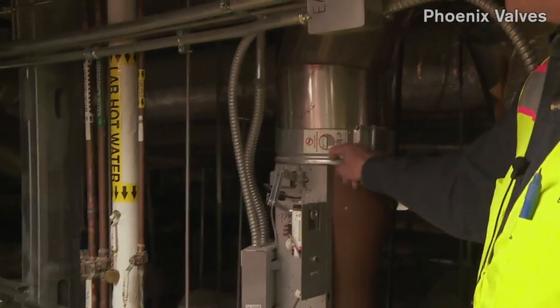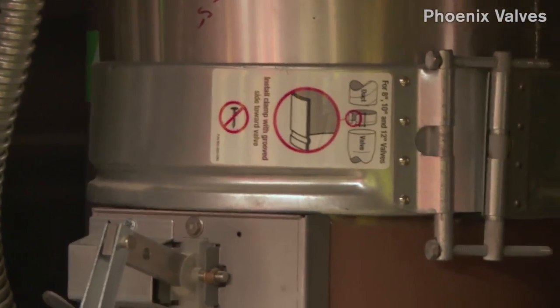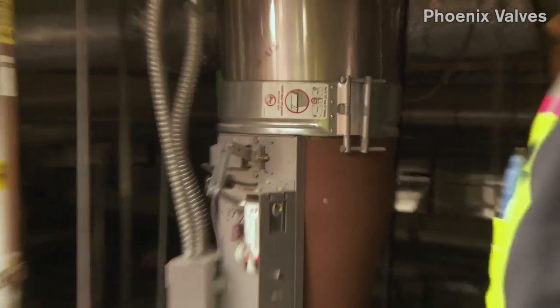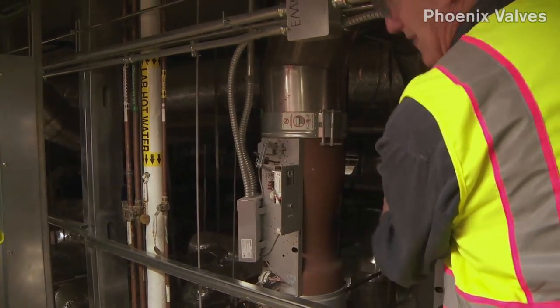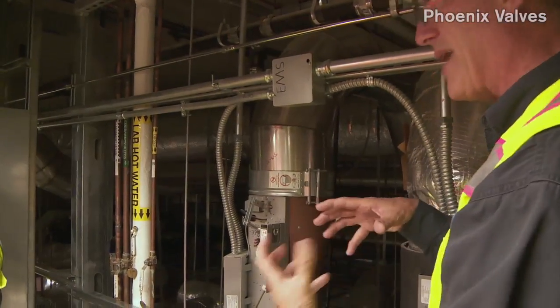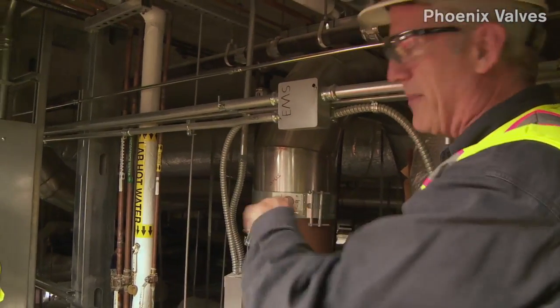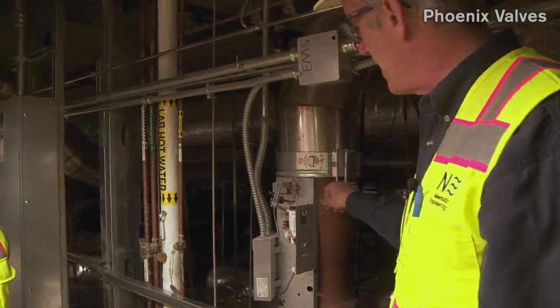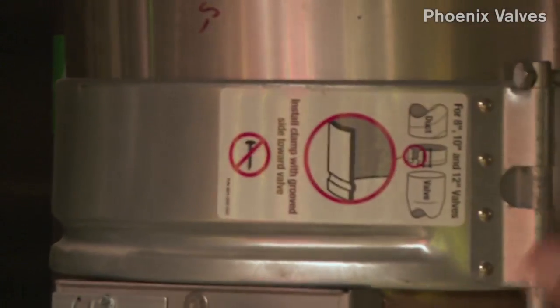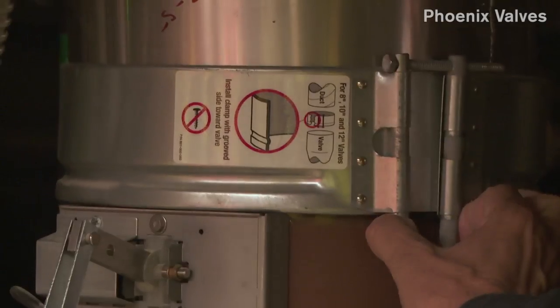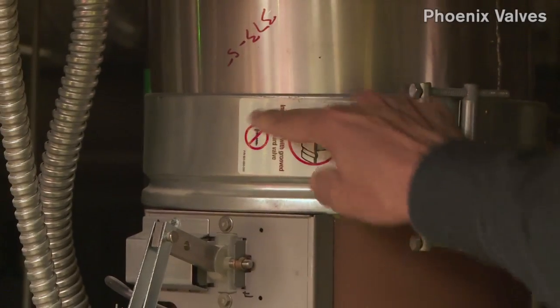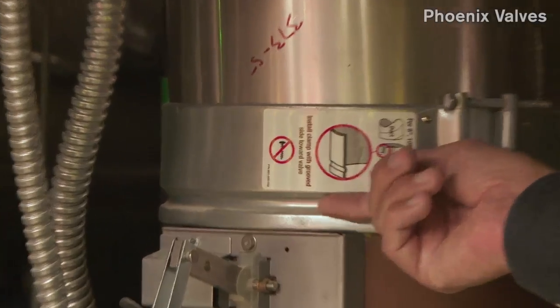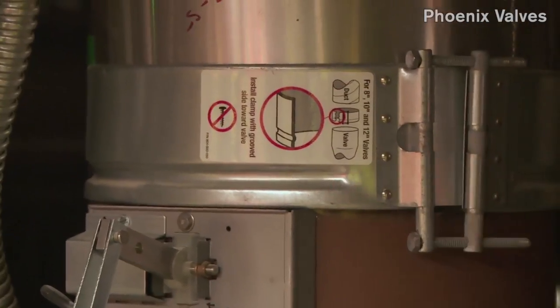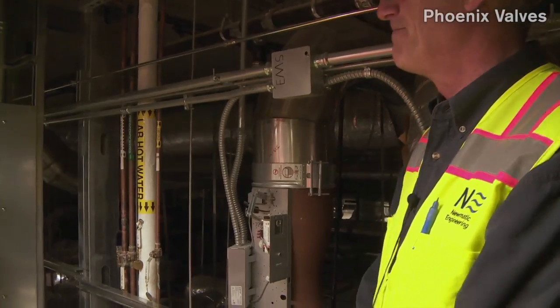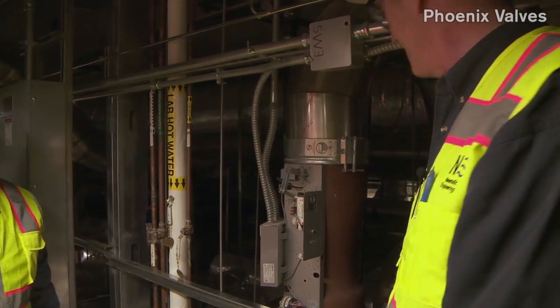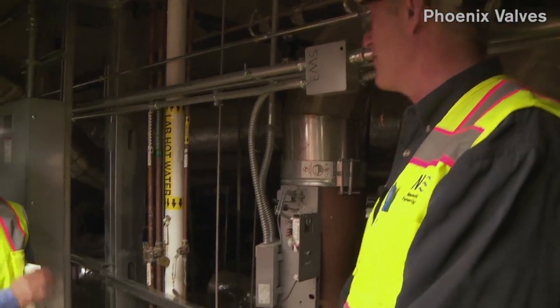This is a drawband clamp. When you have a corrosion resistant valve, that might be a hood or a biosafety cabinet. Normally you can attach our valve by just putting Tek screws right through the ductwork and our valve. Our valve slips right inside ductwork, so you just drive a Tek screw, a little bit of pookie, and you're done. On the exhaust, you don't want to penetrate our phenolic coating. So you use this two-bolt drawband clamp. You tighten it on the duct, you tighten it on the valve. The valve is slightly smaller than the duct, so it binds here, and then it's got this knuckle in there to bite onto the valve body. So it bites both places without penetrating the coating of the valve. There's also tape in here too. And we put some Viton tape underneath for corrosion resistance.